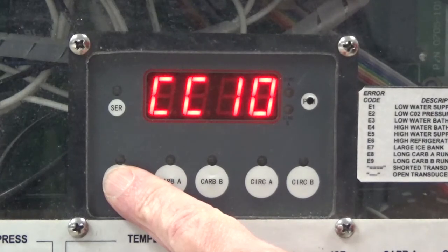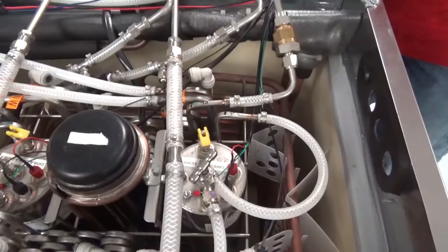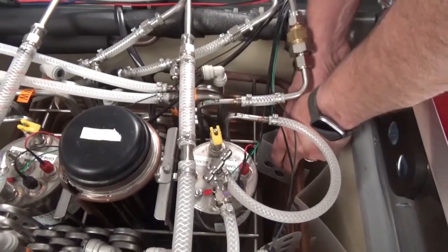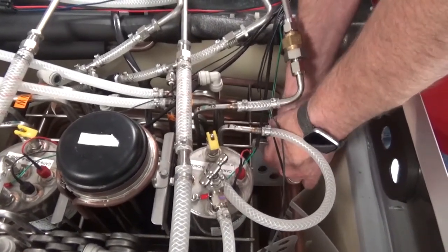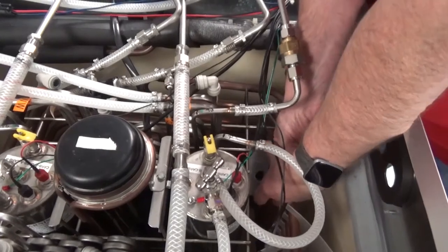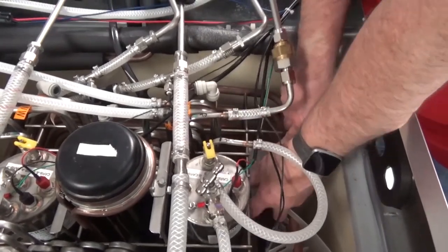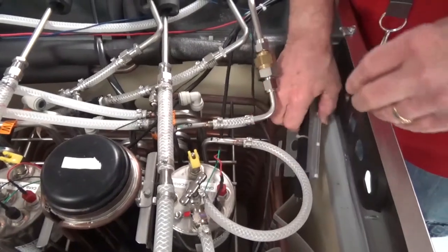If it reads anything else, check the ice bank probe. You can remove the ice bank control probe from the water bath. You squeeze the mounting bracket flat, turn it 90 degrees, and pull it out of the water with the probe attached.